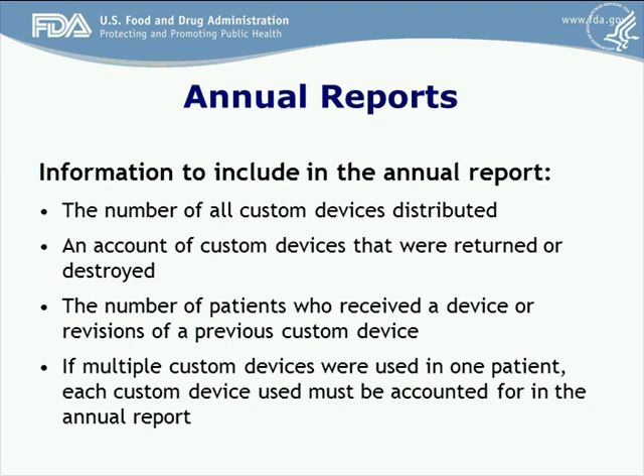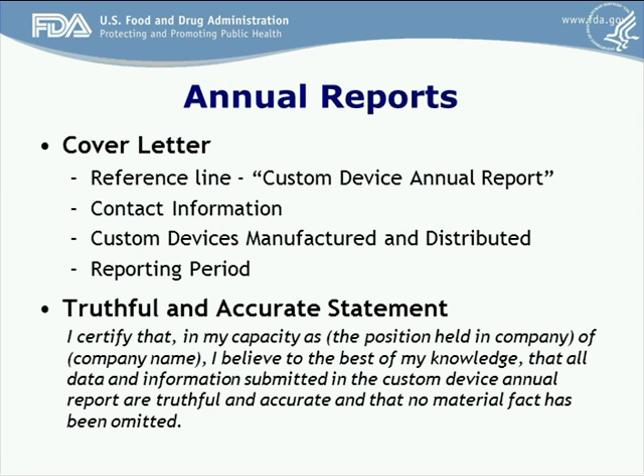Information that should be included in the annual report includes: the number of all custom devices distributed, an account of custom devices that were returned or destroyed, and the number of patients who received the device or revisions of a previous custom device. If multiple custom devices were used in one patient, each must be accounted for. A cover letter should accompany the annual report containing a reference line stating 'custom device annual report,' contact information, the number of custom devices manufactured and distributed, and the reporting period. The annual report must also contain a truthful and accurate statement using the language provided in Appendix 2 of the guidance.